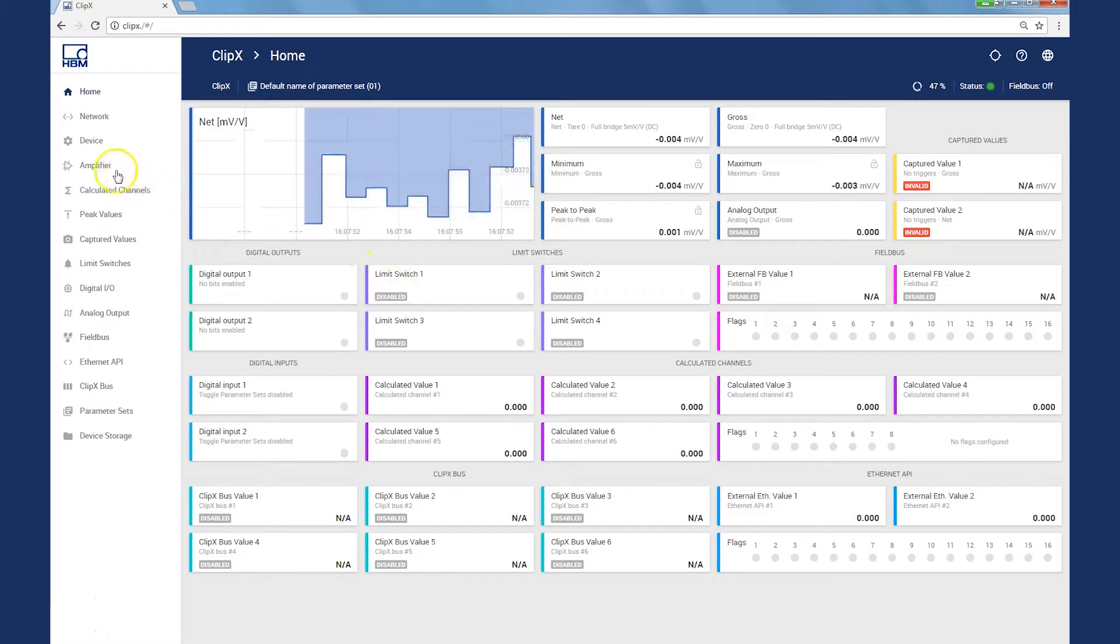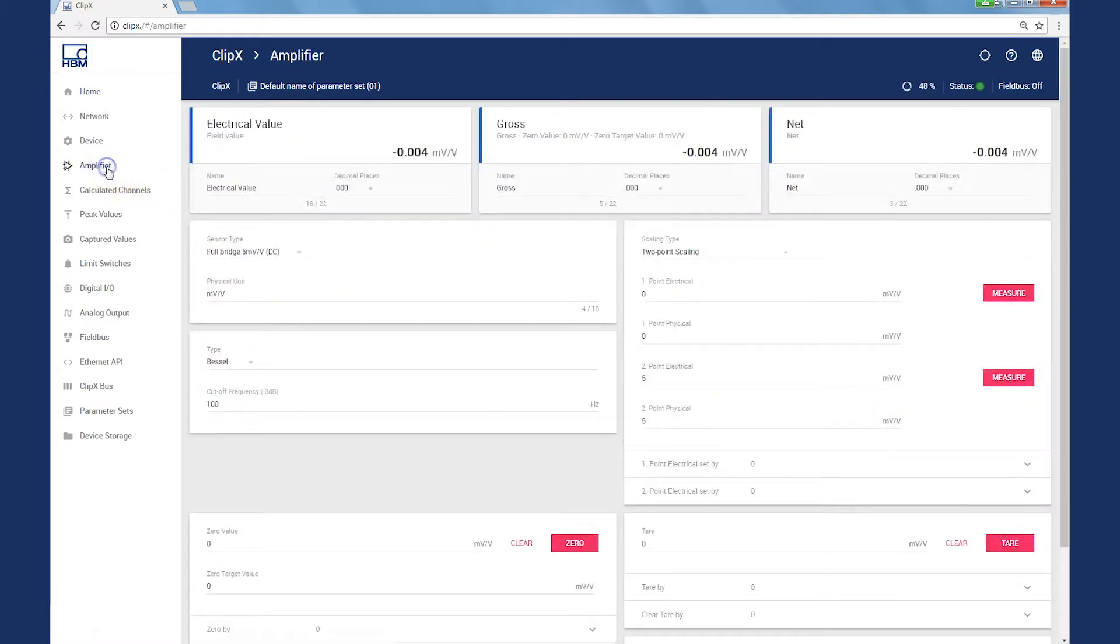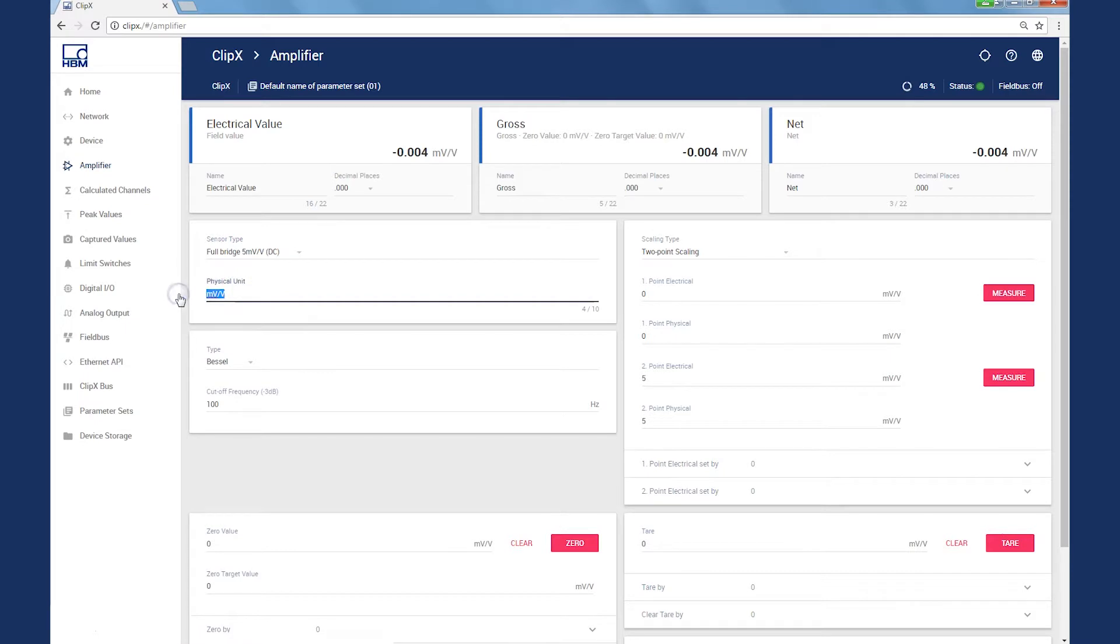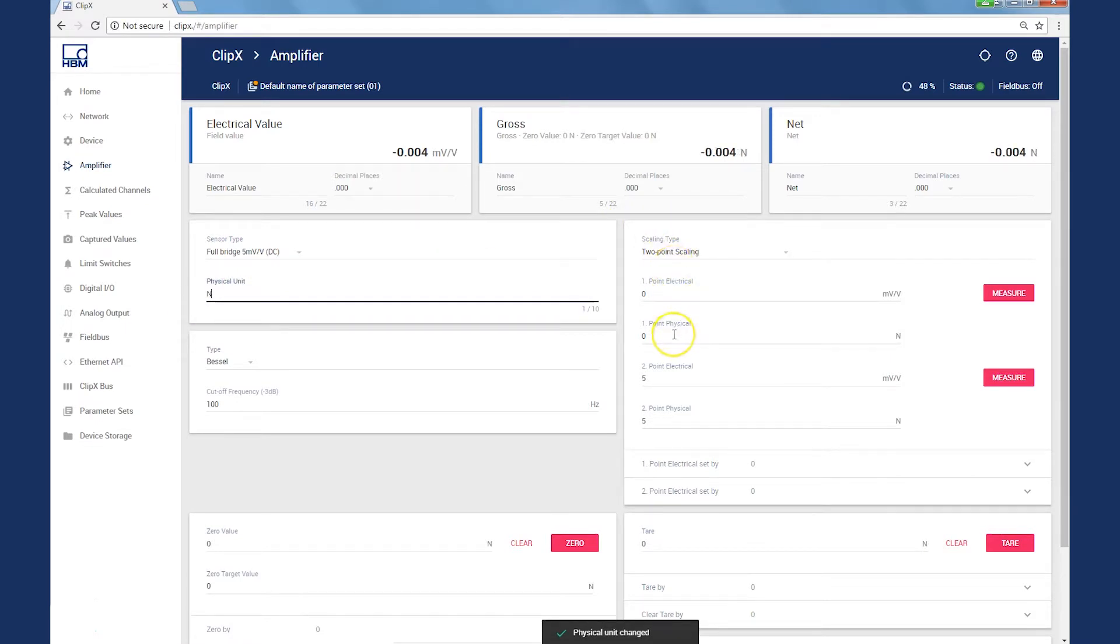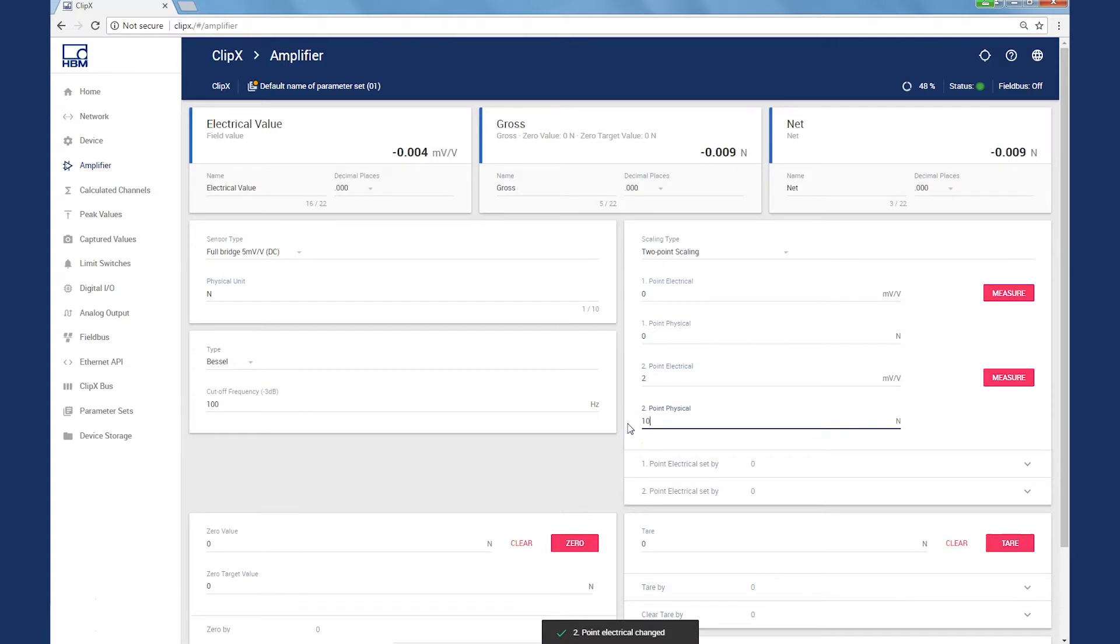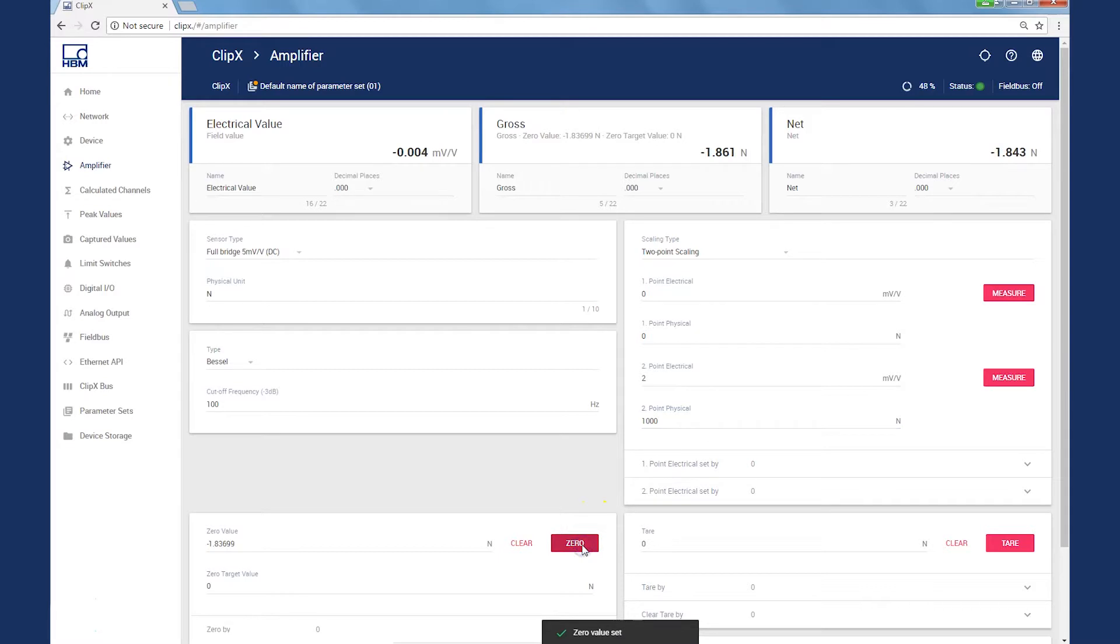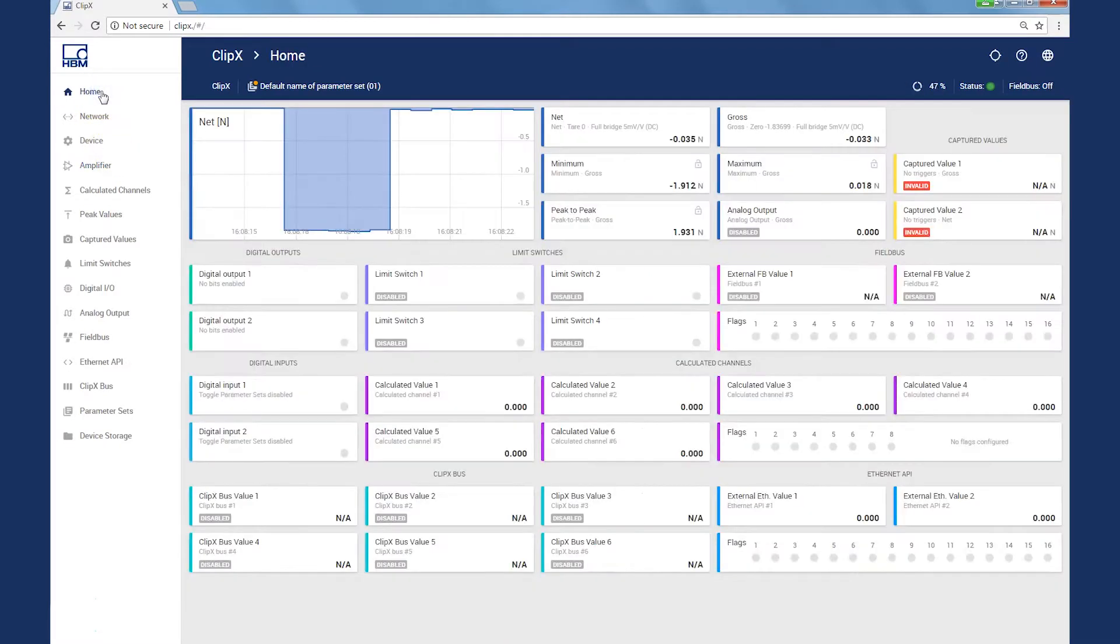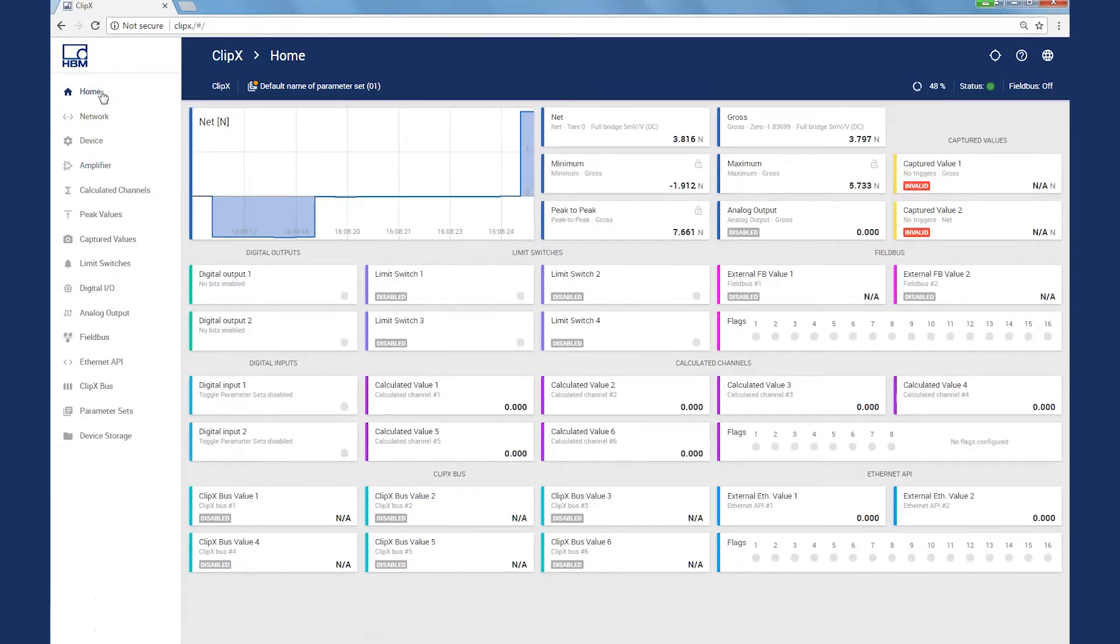All settings and initializations can be made on the home page itself. On the amplifier side, I now select the desired measuring range and the appropriate unit. As a two-point scaling, I've set a range of 2 mV per volt for 1000 N for the force sensor S9M. Finally, I set the signal to zero and my measurement value is immediately displayed, which is also projected on the home page.